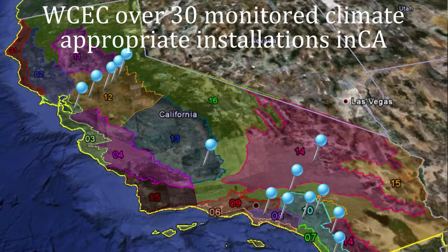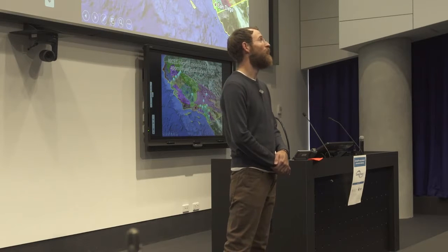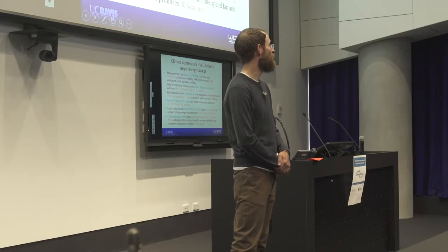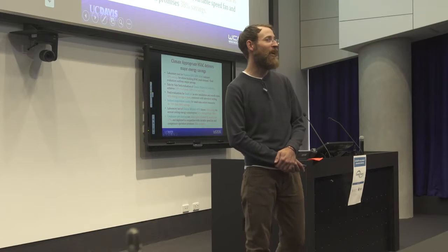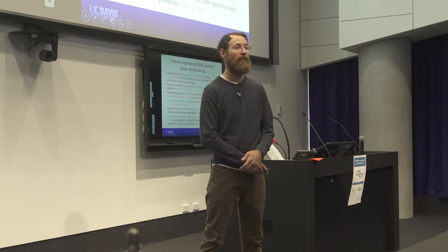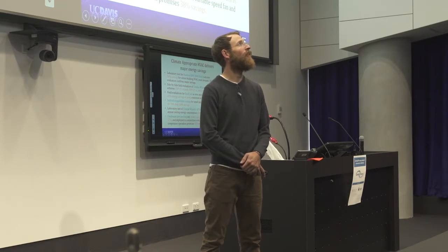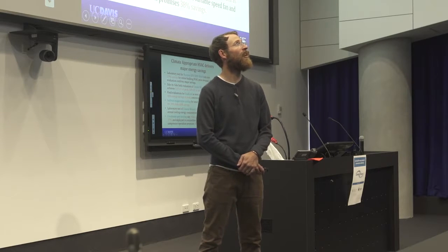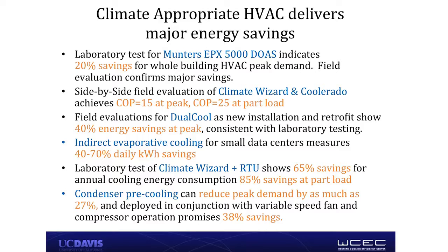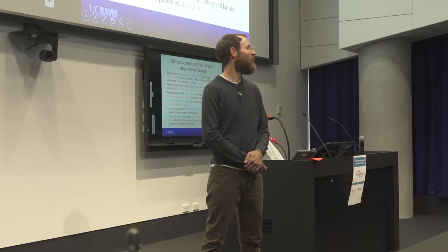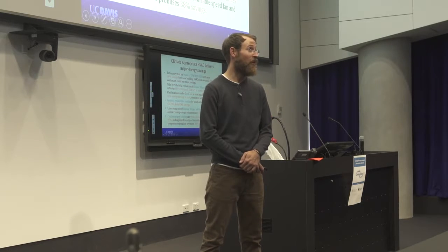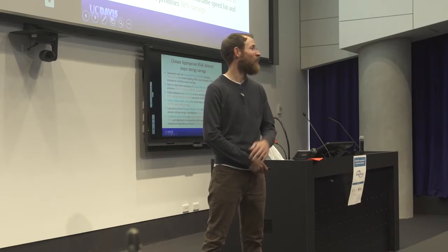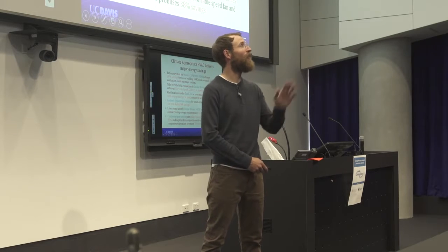Since that very first entry, we've conducted a number of other laboratory tests of different technologies and more than 30 monitored field installations of what we call climate-appropriate technologies just in California alone. And we've learned a lot. The major takeaway, I won't run through all of this, is that in every study we're showing some major energy savings using this type of technology. These are along the same numbers that were being presented earlier as you were looking at the demonstration, but we ran a side-by-side evaluation of the Climate Wizard and the Coolerado system, and it showed a cooling COP of 15 at peak. What they didn't mention is another advantage of that system is that you might reach a COP greater than 25 when you're running at part load. So peak, of course, is incredibly important, but there's huge opportunity during part load when that system can run at variable speed.